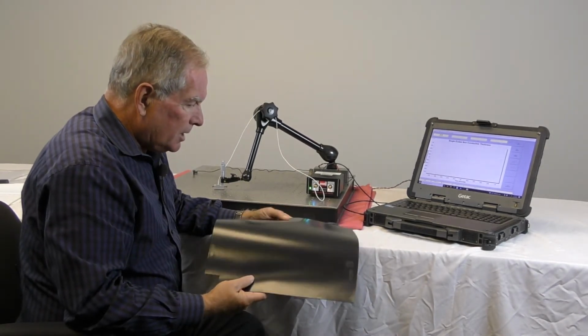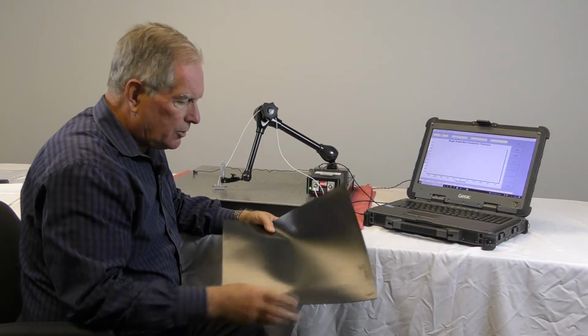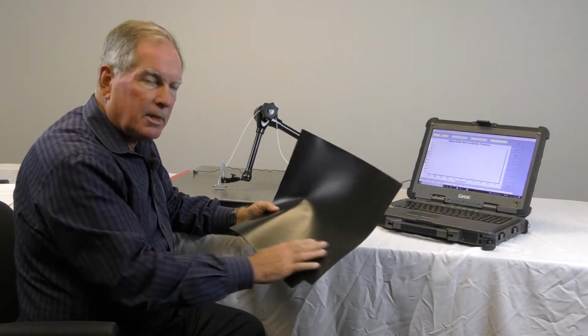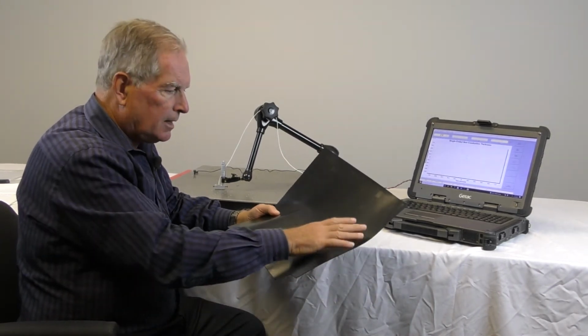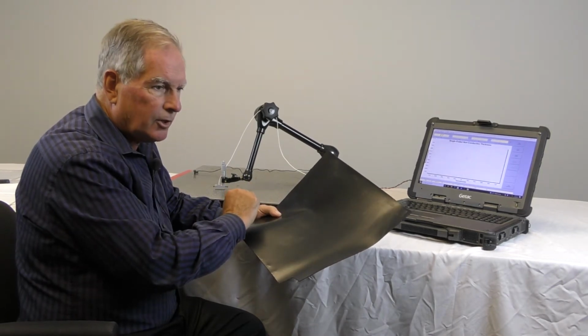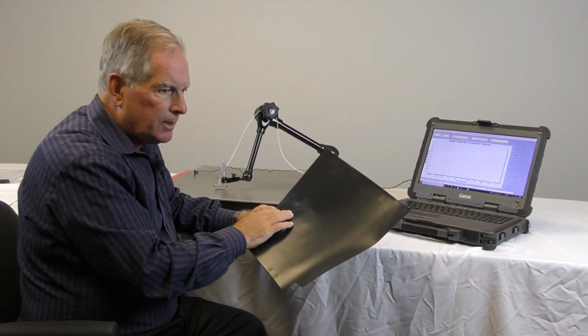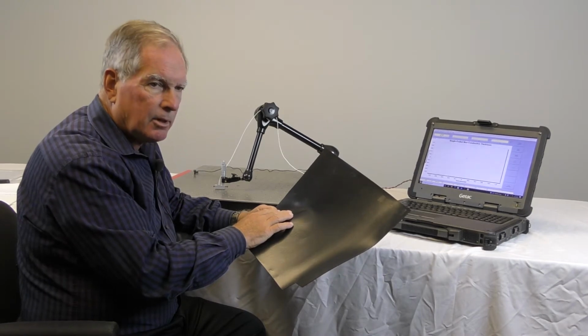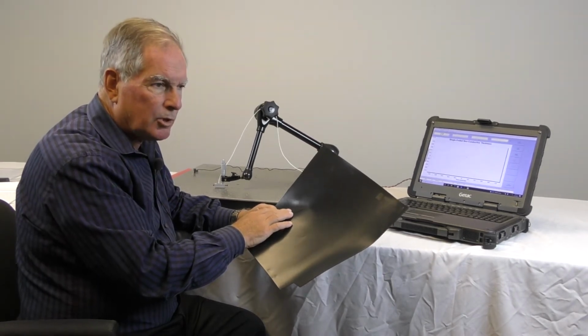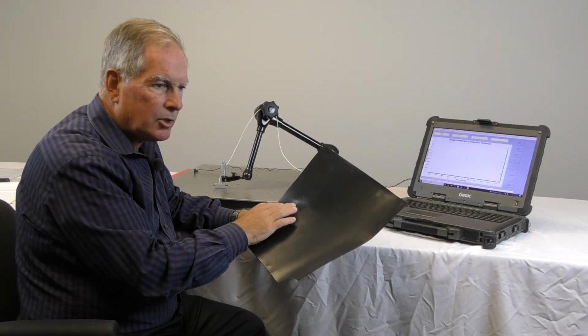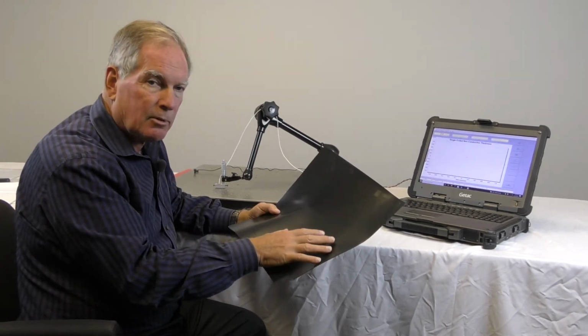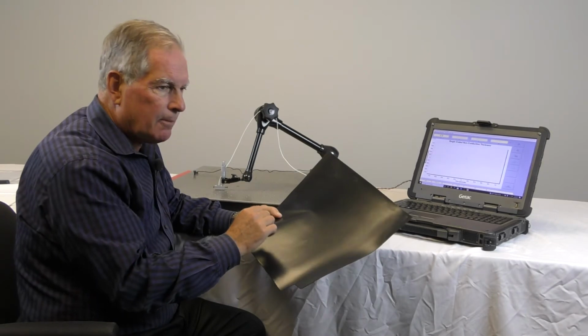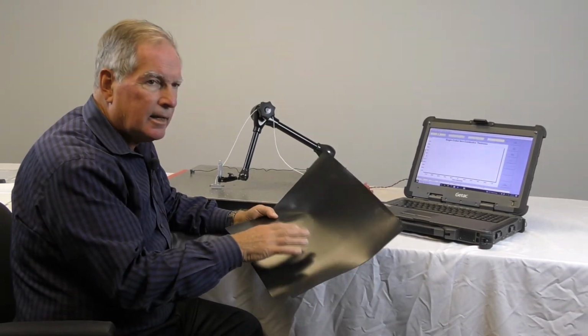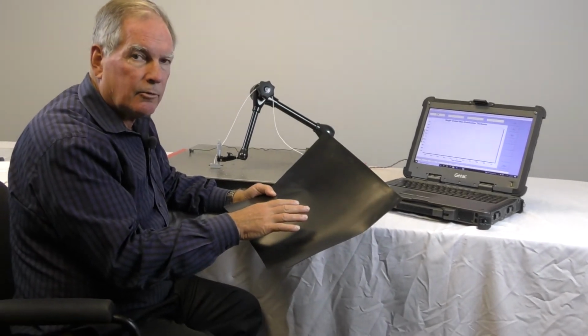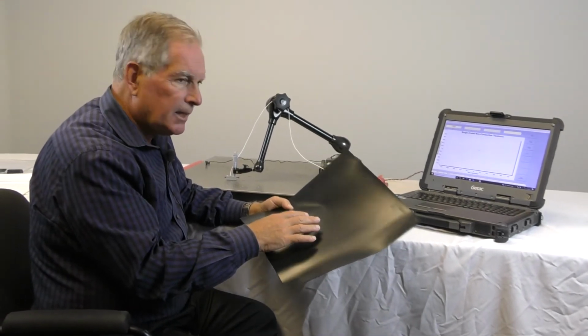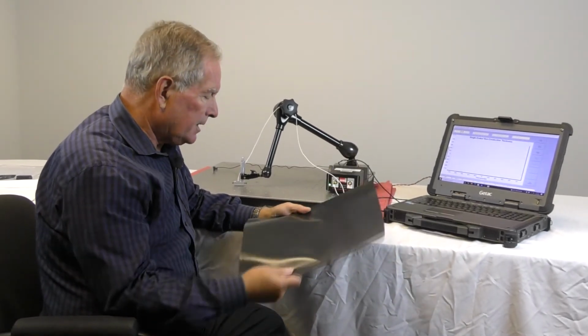The other thing is it should be a homogeneous material. So the dielectric constant or the makeup needs to be consistent. It can't be a striation of different materials. If you think about something like a conglomerate material, perhaps pressboard or something like that, where you have different thicknesses, different densities of materials that are pressed together, for example like epoxies and wood and things like that, that's not a good idea for measuring the thickness. You'd have to use lasers for something like that.